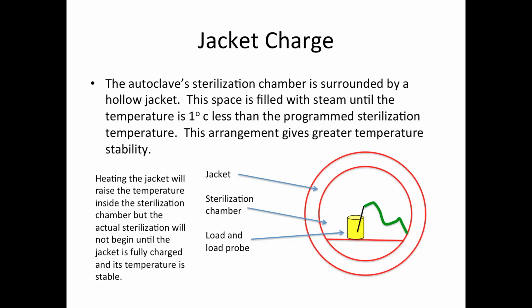The first phase of the cycle is the jacket charge. Now, the autoclave sterilization chamber is surrounded by a hollow jacket. This space is filled with steam until the temperature is 1 degree less than the programmed sterilization temperature. And this arrangement gives us a very good temperature stability in the sterilization chamber.